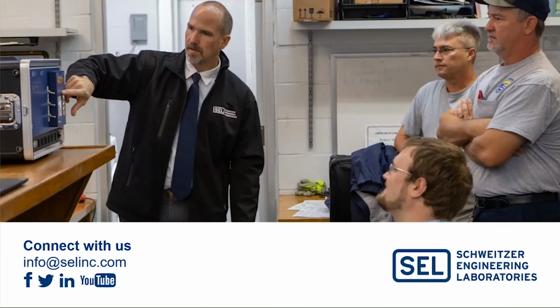Absolutely, Richard. Originally we wrote all the logic for the pump controller just in logic for the 2411P. Now all of that logic has been emptied and pushed into the firmware, so now we have a ton of extra logic to do some really neat things for any of these add-on applications at a lift station or pump station where you need additional control, automation, any kind of sophisticated stuff.